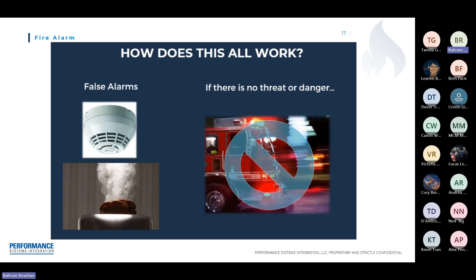Once you have confirmed it is a false alarm, silence the fire alarm by pressing silence on the annunciator or at the fire alarm control panel. Then call your central station and let them know you had a false alarm. The central station will let the fire department know it was a false alarm. Once this is completed, you can reset the fire alarm system to a normal state.